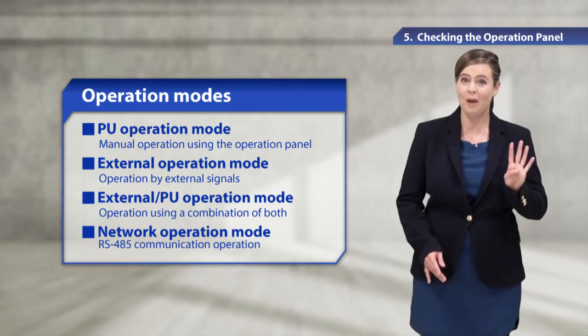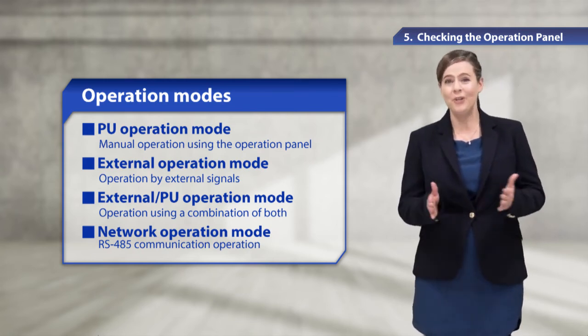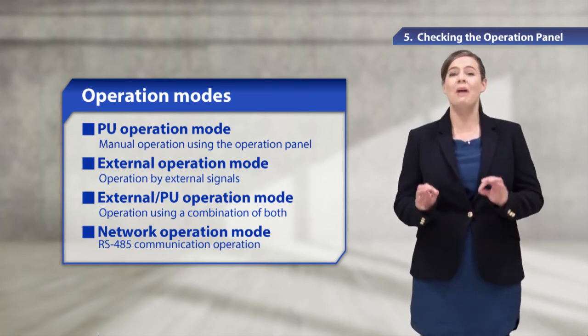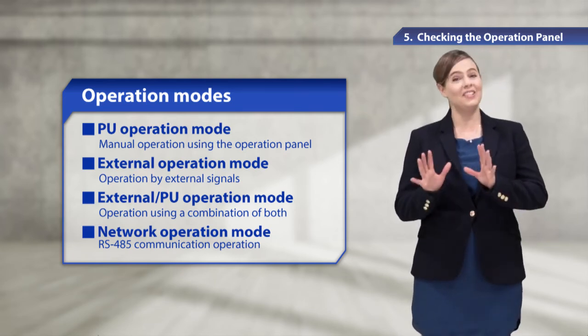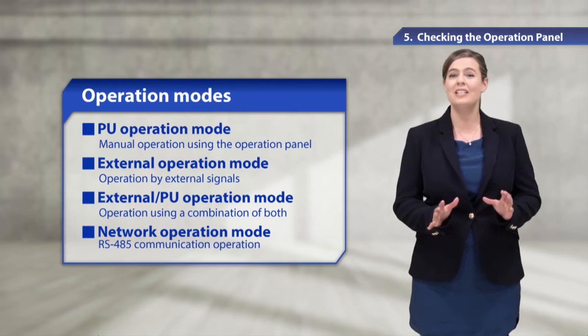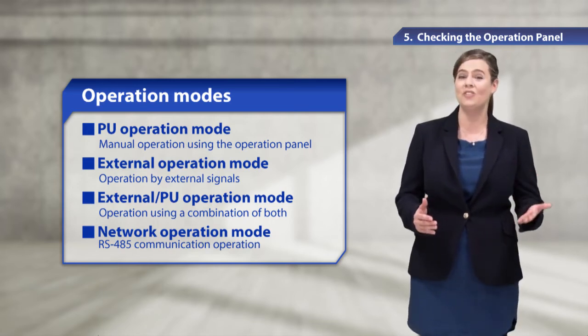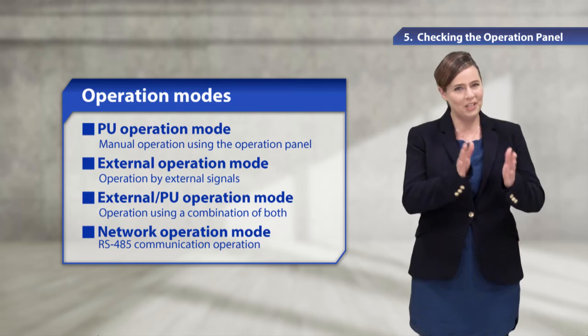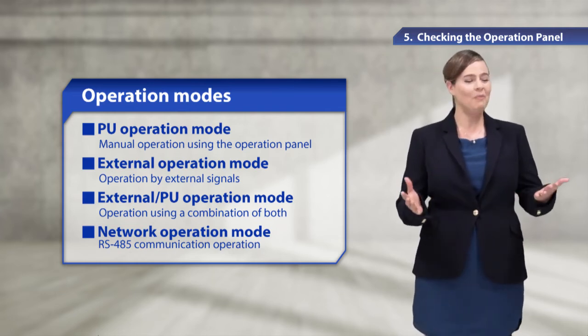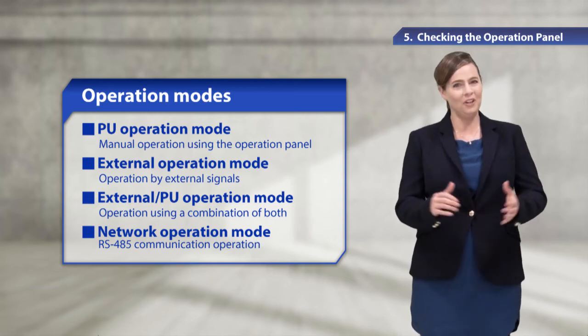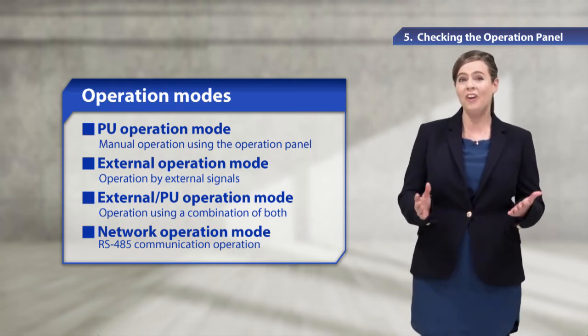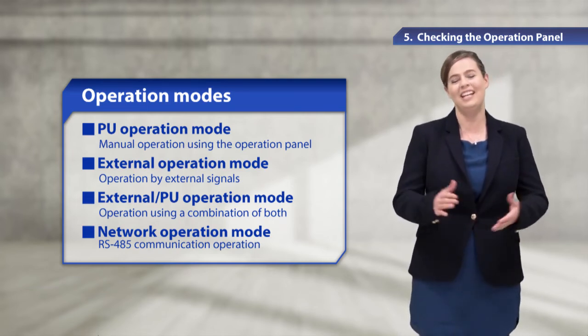I'll first introduce the operation modes. The inverter has four operation modes. The PU operation mode is for manual operation using the operation panel. The external operation mode is for operation using external signals. The external PU operation mode is for operation using a combination of both, and the network operation mode is for RS-485 communication operation.